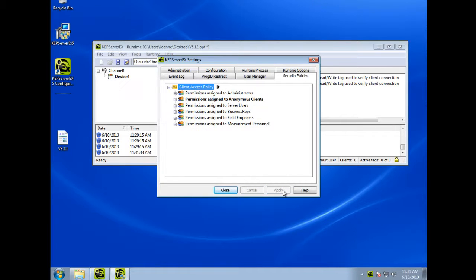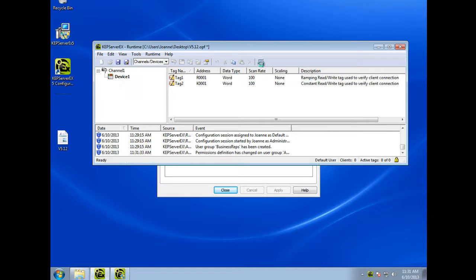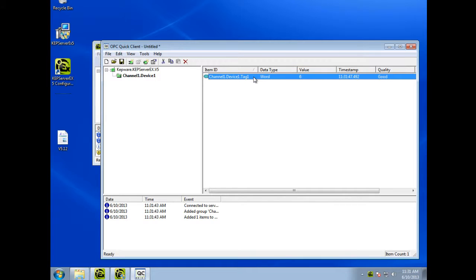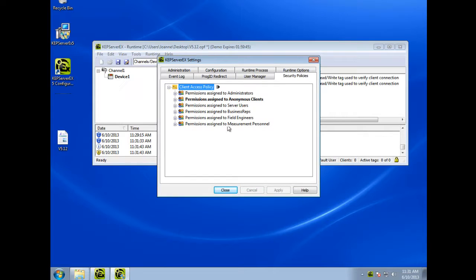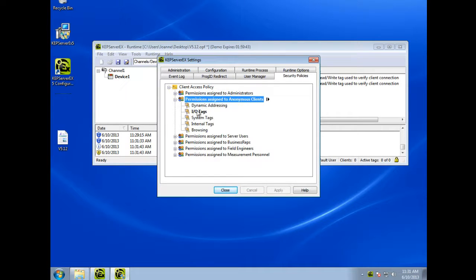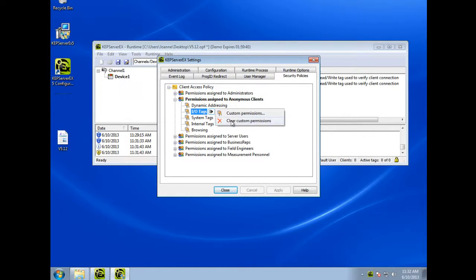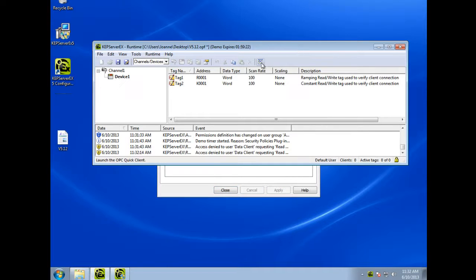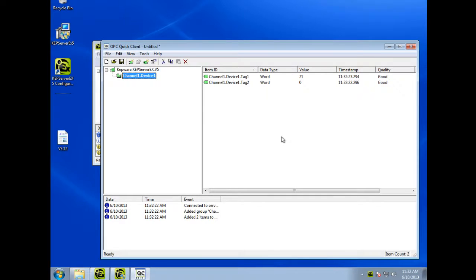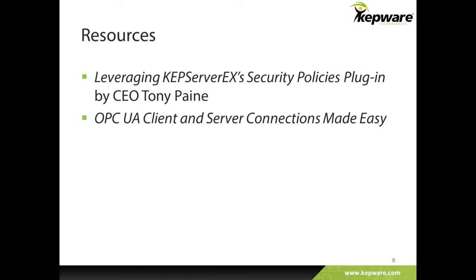If I apply the security settings and open Kepware's OPC DA quick client, I see now that only tag 1 from this device is available. If I toggle back the settings and clear custom permissions for IO tags, the client is given full access and tag 2 appears again. For more information on these new security options, please refer to 'Leveraging KepServer EX's Security Policies plugin,' written by Kepware's CEO Tony Paine.